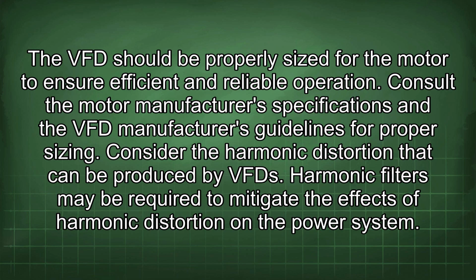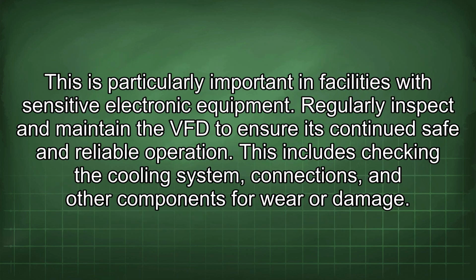Harmonic filters may be required to mitigate the effects of harmonic distortion on the power system. This is particularly important in facilities with sensitive electronic equipment. Regularly inspect and maintain the VFD to ensure its continued safe and reliable operation. This includes checking the cooling system, connections, and other components for wear or damage.